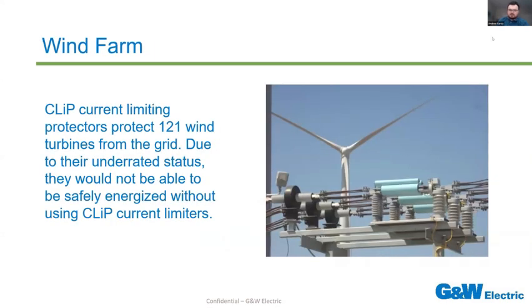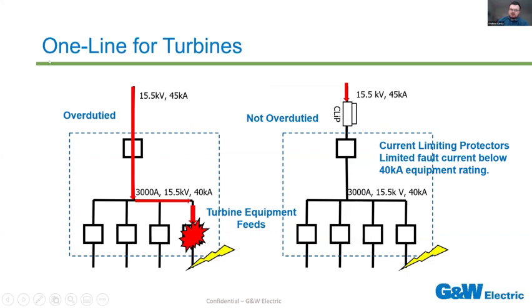Here's another example of a wind farm where clips were used to protect about 121 wind turbines from the grid. They found out most of the way through a project, their utility suddenly reached out to them and let them know that there was a lot more fault current available than was previously disclosed to them. It ended up that a lot of their turbines were underrated. They found out that they wouldn't be able to actually energize their equipment and go online without using some kind of current limiting device. They ended up figuring out that clips were the best solution for them, which they then integrated in their system. They were able to energize the project on time and get going. So here's exactly how that would look.